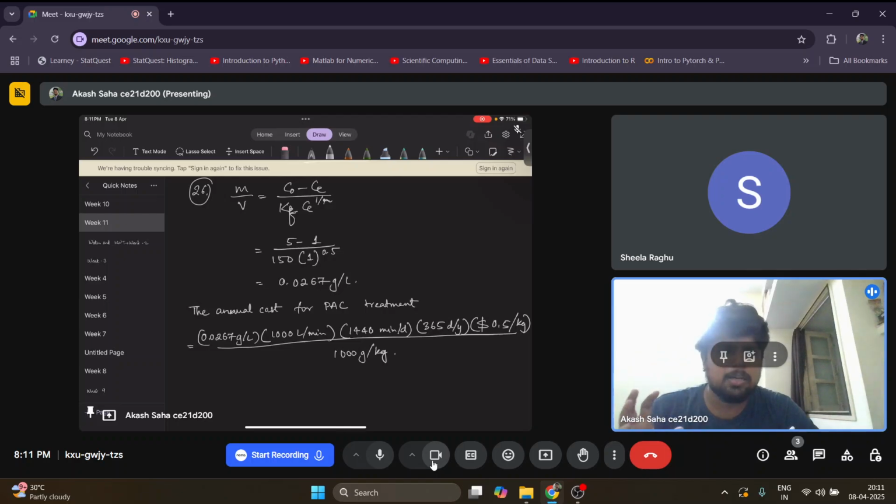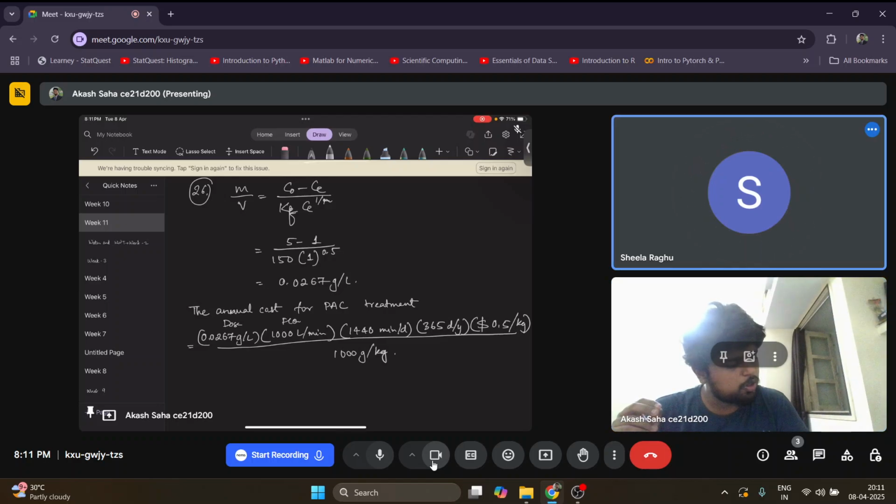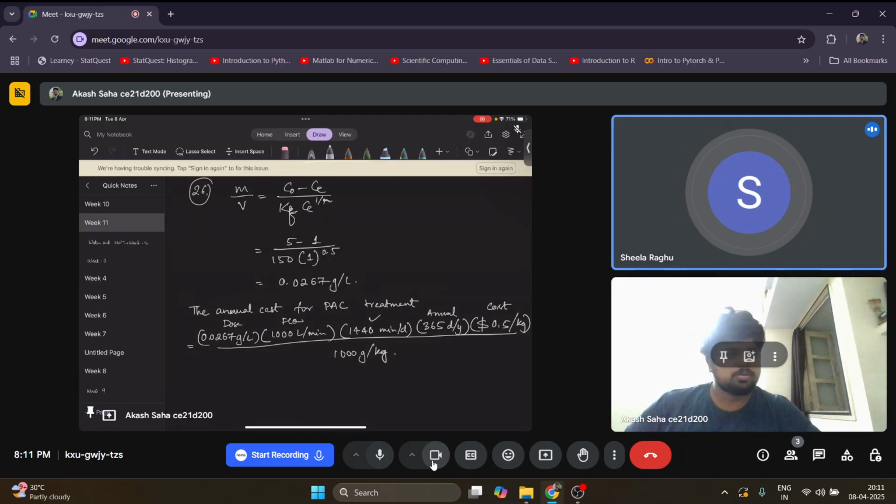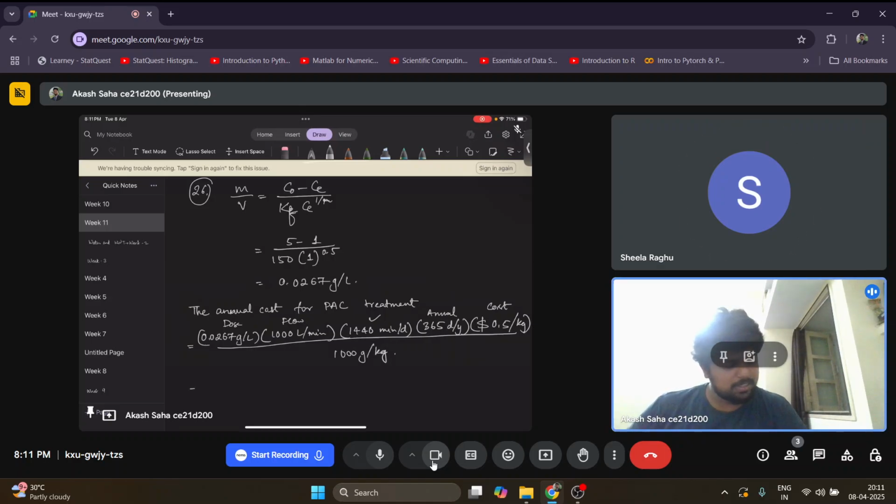First the dose into the flow, then time conversion into annually, how many days per year, the cost. Just multiply everything, and in dollars you will get the answer, 7008. So this much money you have to spend for the treatment, very direct.